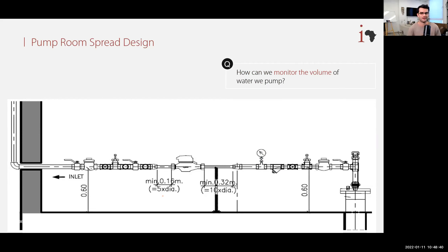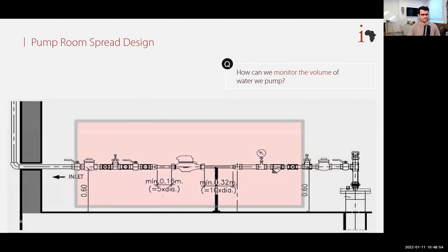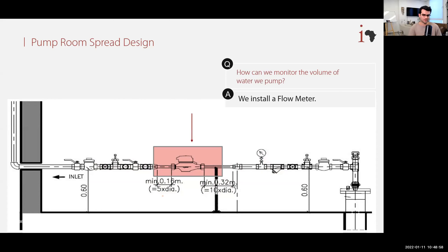To monitor how our projects are doing and whether the village is getting clean water, we need to monitor the volume of water being pumped. We install a flow meter — one of the most important accessories in the pump room. It's connected by wire to the monitoring box and transmits electrical pulses back, which relay data to Israel on how much water has flowed in a project. The flow meter works via a mechanical wheel that spins with the water, sending a pulse every ~100 liters.